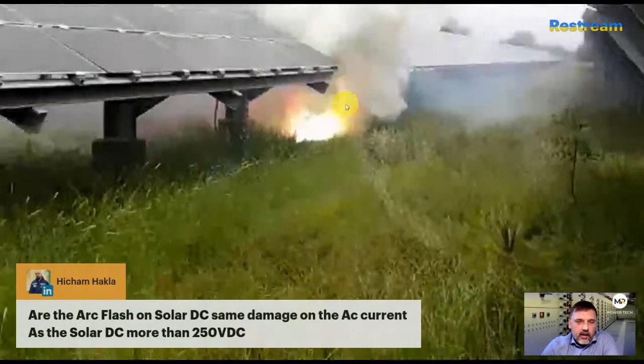It's not given. But if you look at it, you will see that there is a constant power flowing. Energy very much depends on the configuration of the network. Typically, they are not like 40 calories because you usually have less available short-circuit power, but on a 50 megawatt system it might be different. And you also have power electronics that are supposed to limit the current. It's getting complicated at some point. But typically, DC should be higher than AC because you don't have a sine wave, it's constant, and we don't have a zero crossing, and it's also very hard to trip at some point, if you don't have proper equipment.